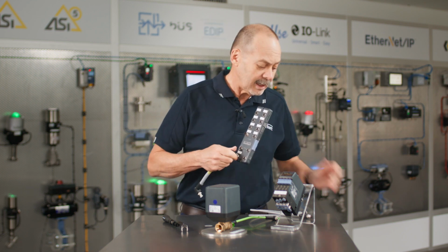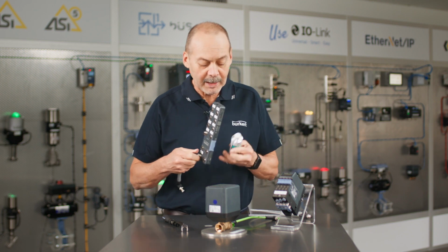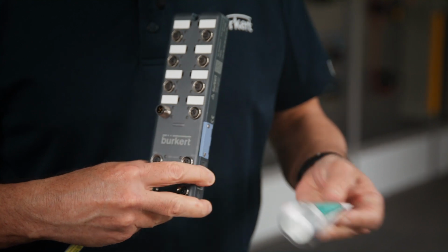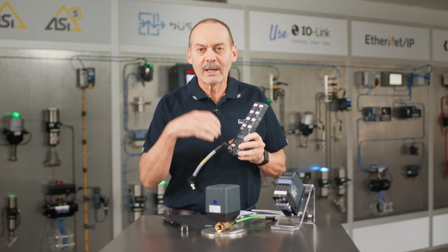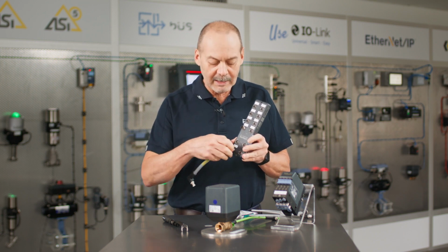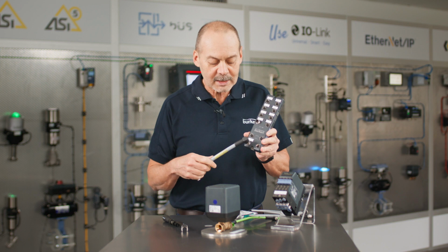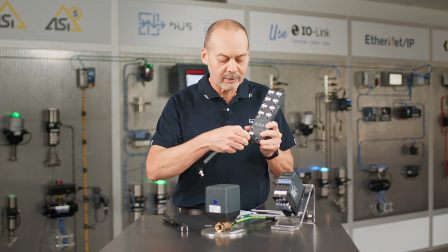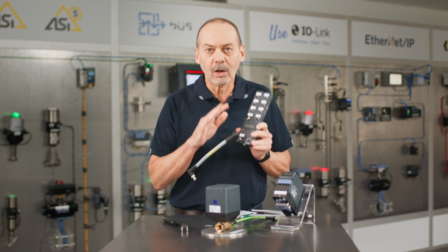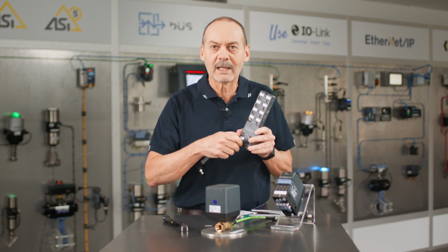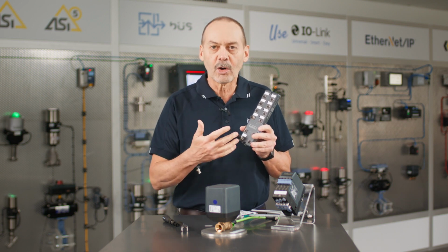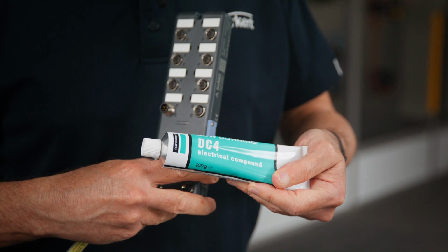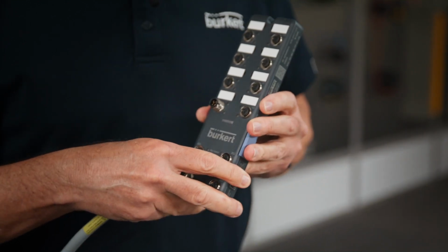Lastly, if you are in a really wet environment where you know there's a lot of moisture or steam or things like that, then it doesn't hurt to put a little bit of grease. Now we recommend the Molykote 4 or Dow Corning silicone grease. Do not use hard silicones because they will eventually just dry and crack and you end up with wicking going through them. A silicone grease will actually fill any air cavities, and you can use that right through from ASi cables right through to connectors. You don't use it a lot. You're just lubricating and moistening the O-ring a little bit and making sure that there's no area for liquid ingress, because you find if it's a proper electrical compound silicone grease, it will resist any ingress of water.